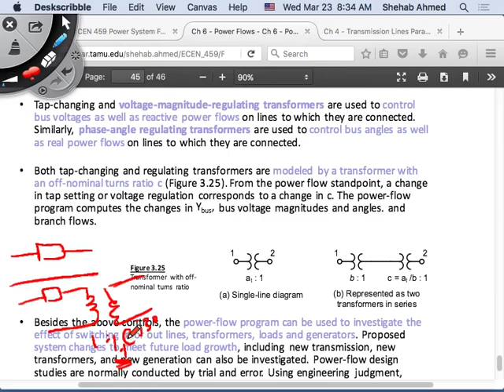When you change your tap, you don't change your base voltage or base power - no, base power never changes for the system, and the base voltage will not change. That's why we end up with a 1.1 here, or 1.2, or 1.3 - something greater than the base we originally had. That's really the effect.